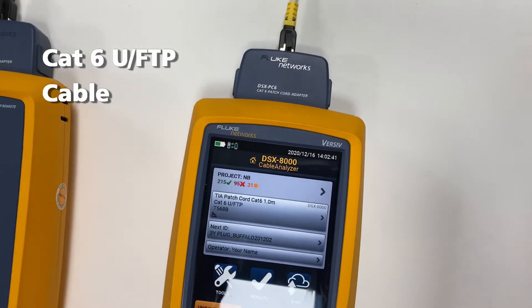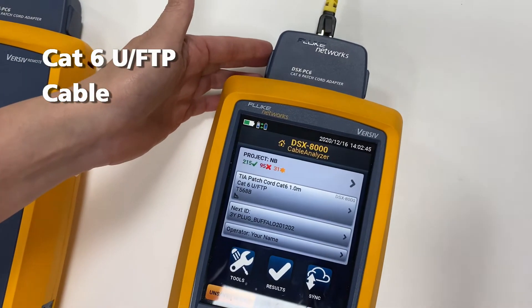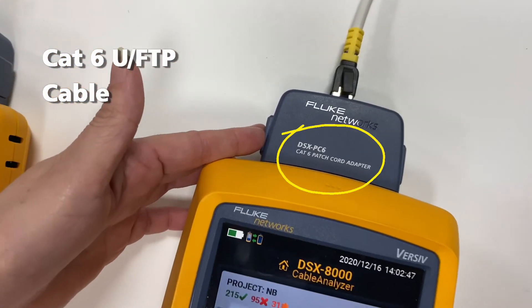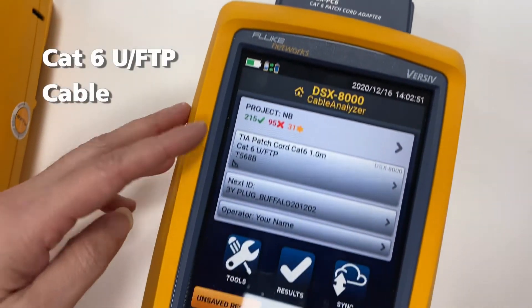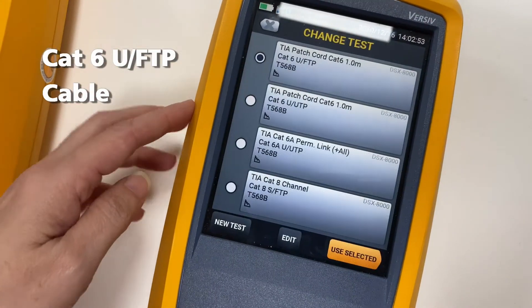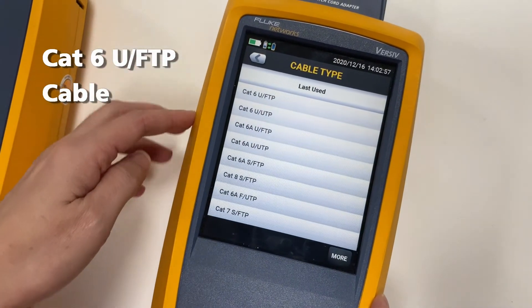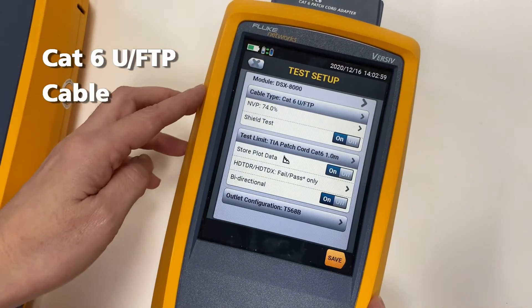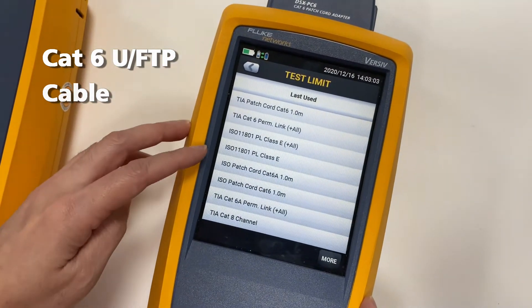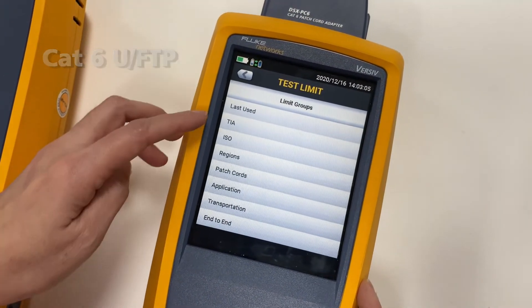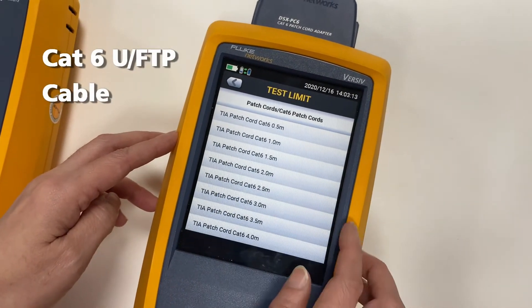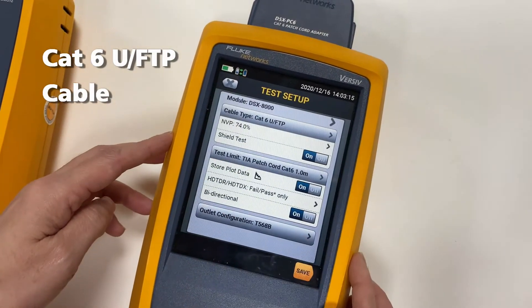Now we are going to show you how we do the Cat6 U/FTP patch cord component test. First, make sure the adapter is correct for the Cat6 patch cord. Then we will set up the cable type — choose Edit and choose the right cable for Cat6 U/FTP, then choose the test limit. We set up the parameter for TIA Cat6 1 meter.